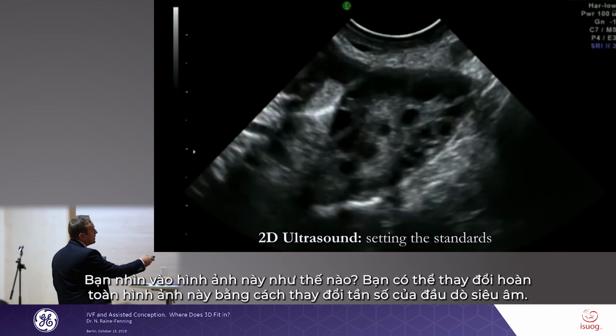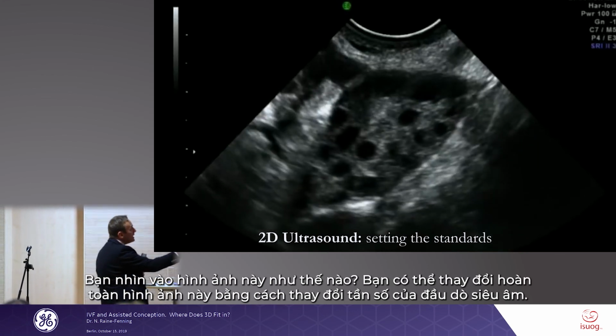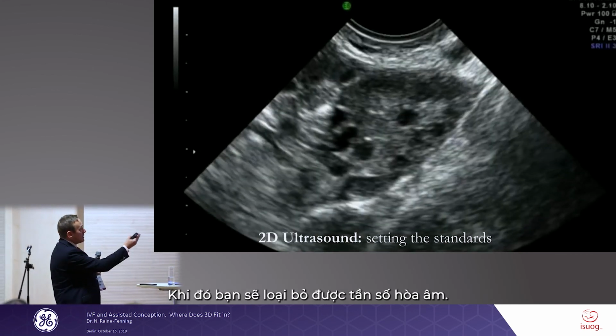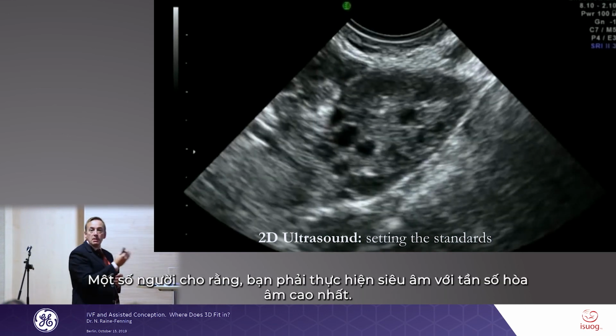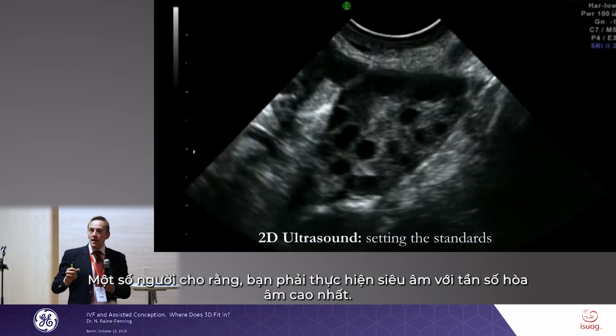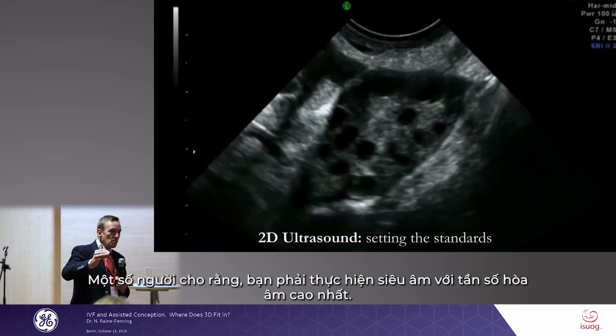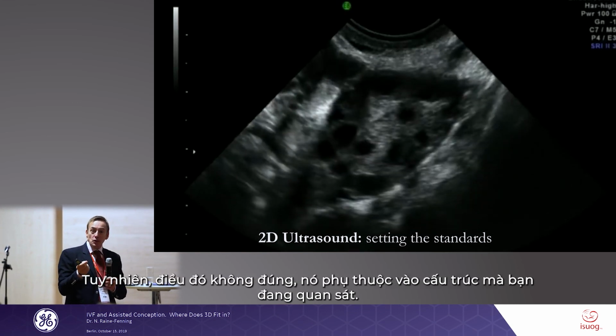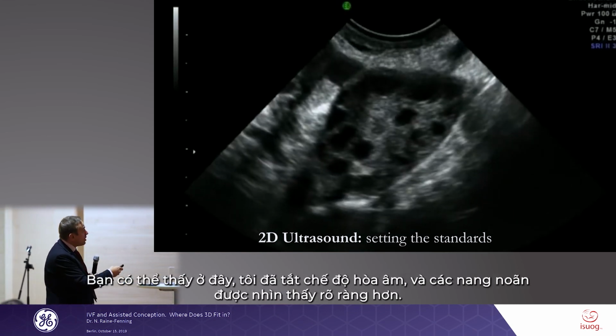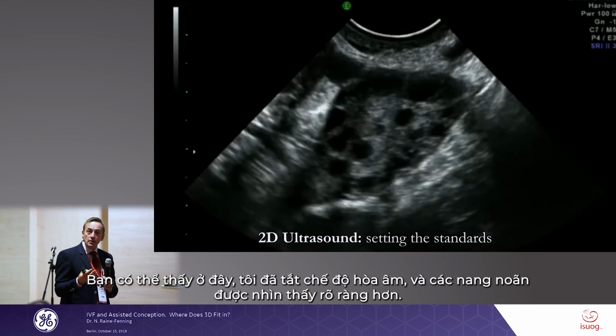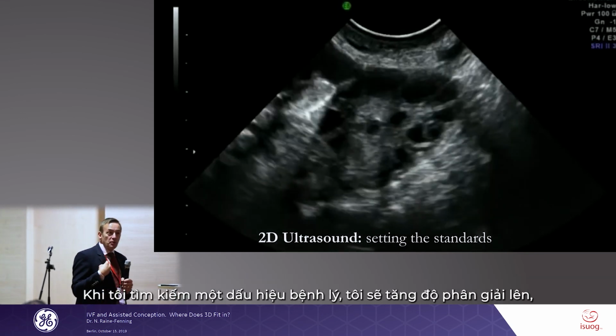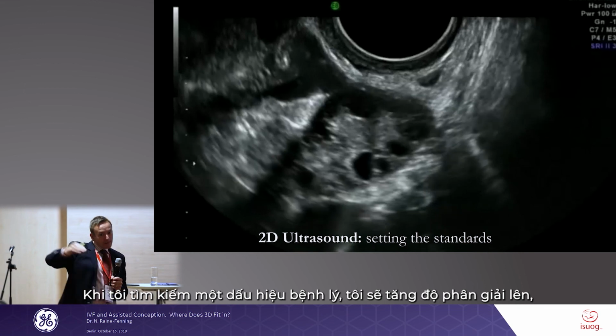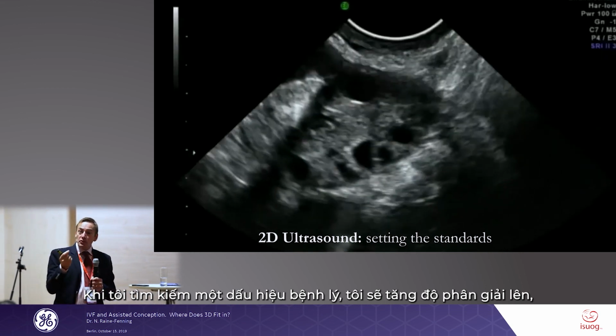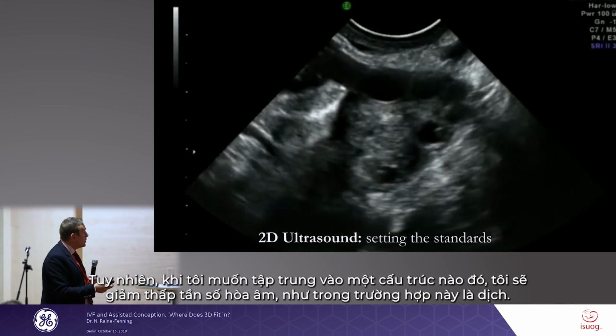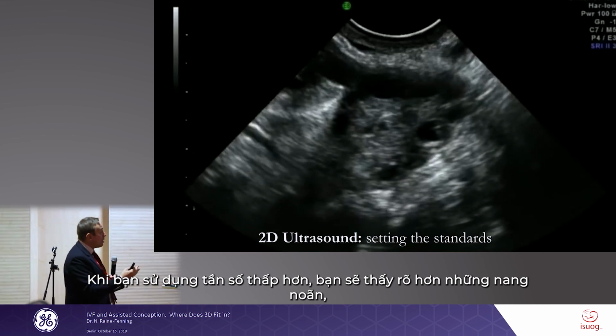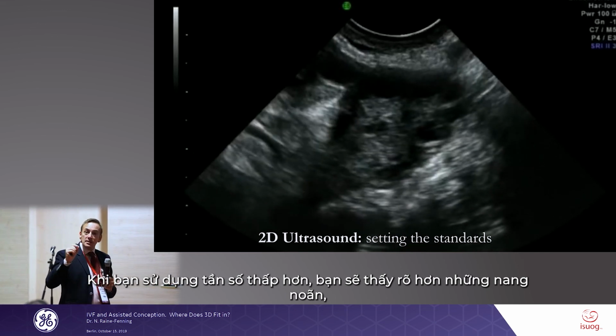So this is just a quick video to show you how you can completely modify the image by changing your frequency. Harmonics has been removed now. People say you must scan with harmonics, you must scan highest frequency, highest harmonic. That's not true. It depends what you're looking at. And you can see here when you switch the harmonics off, the follicles become more apparent. So if I'm looking for pathology and I want resolution, get up your bandwidth. But if I want to accentuate something, in this case fluid, then using maybe a lower harmonic or a lower frequency will allow you to see those follicles.